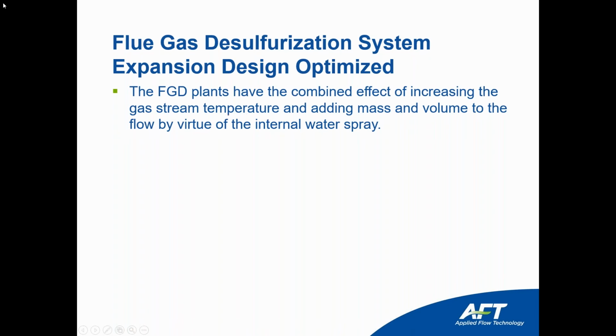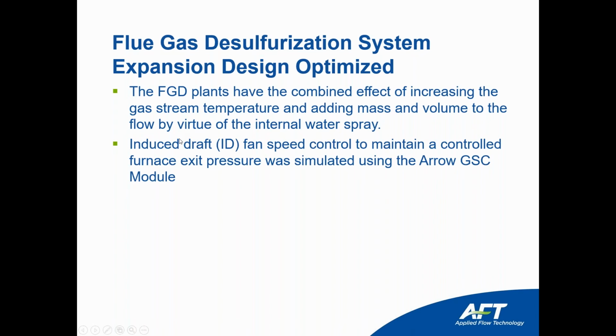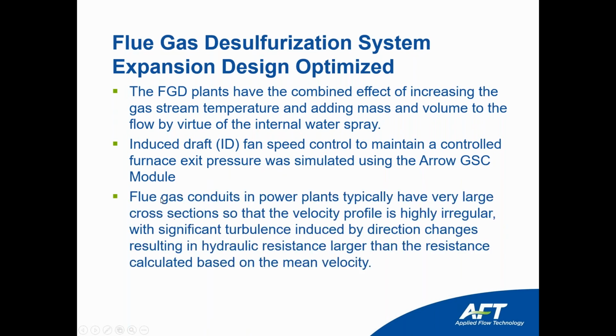Second challenge. The flue gas desulfurization plants have the combined effect of increasing the gas stream temperature and adding mass and volume to the flow by virtue of internal water spray. Another challenge was that an induced draft fan speed control to maintain a controlled furnace exit temperature was simulated, and this is where GSC was used to simulate this.